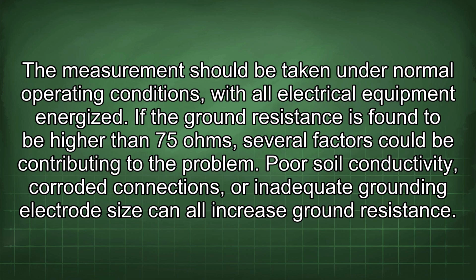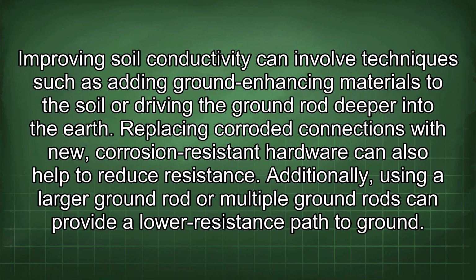If the ground resistance is found to be higher than 75 ohms, several factors could be contributing to the problem. Poor soil conductivity, corroded connections, or inadequate grounding electrode size can all increase ground resistance. Improving soil conductivity can involve techniques such as adding ground-enhancing materials to the soil or driving the ground rod deeper into the earth. Replacing corroded connections with new, corrosion-resistant hardware can also help to reduce resistance. Additionally, using a larger ground rod or multiple ground rods can provide a lower resistance path to ground.